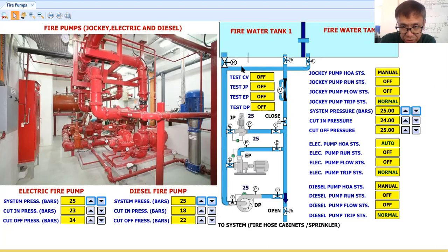Now, as you can see here, I have not shown all the necessary valves, like the zone control valve and the alarm check valves. There are so many valves that need to be installed in the fire pump room. I am just showing you some of the isolation valves, so that if there is a problem with the jockey pump, you can isolate it. Anyway, that is not the purpose of this tutorial. I will not be showing you all the necessary devices or valves that need to be installed in the fire pump piping. Now maybe your question is, how are you going to test these fire pumps?